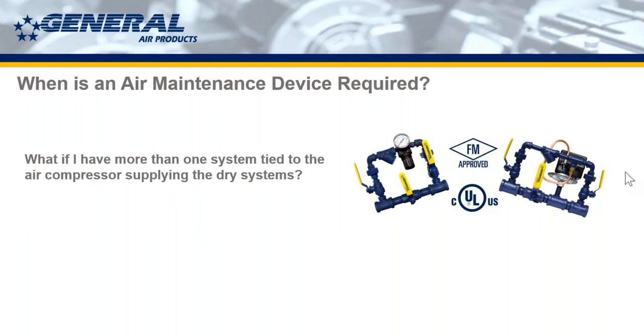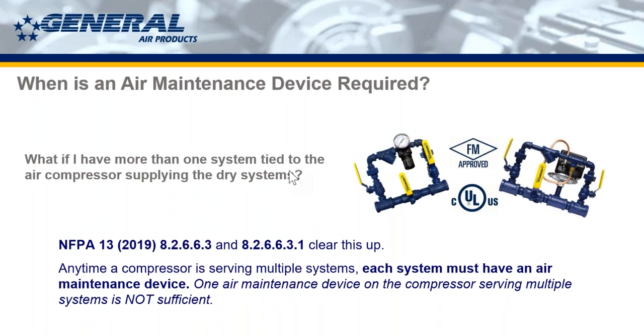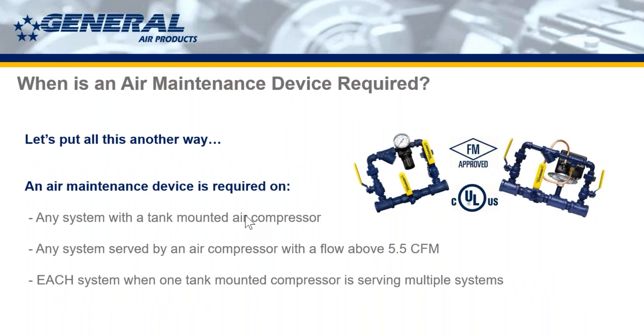That said, 8.2.6.6.3 and 8.2.6.6.3.1 clear up this question of what we would do in these situations in regards to an air maintenance device. And that's anytime a compressor is serving multiple systems, each system must have an air maintenance device. One air maintenance device on the compressor serving multiple systems is not sufficient. Okay. So we do see a lot of people try to do that, where they have one air compressor serving five, six, seven systems, even two systems, and they have one air maintenance device coming out of the air compressor. By the standard, that is not allowed. And you need to have one air maintenance device per dry valve or per riser. And just so you know, when I say dry valve, I mean pre-action valves as well. I just use those terms interchangeably.